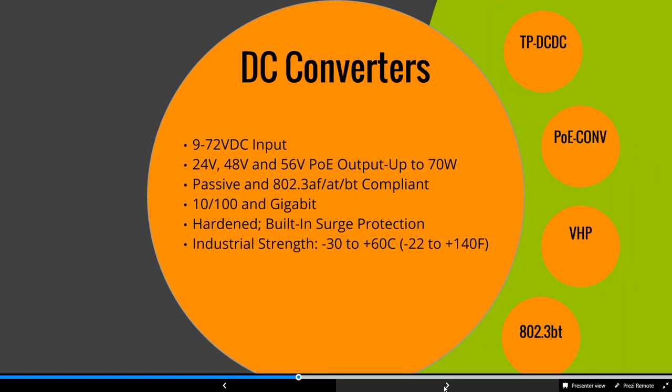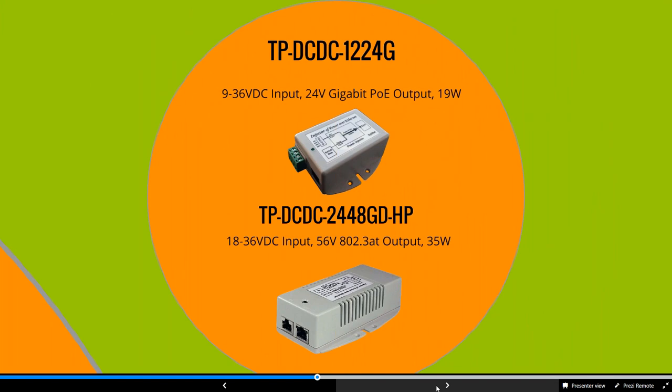We'll start with our DC-to-DC POE injectors — great for when you have a 12 or 24-volt battery bank but need POE output. These accept 9 to 72-volt input with 24, 48, or 56-volt POE output in passive and compliant options. One of our most popular parts is the TP-DCDC-1224G, which takes 9 to 36 volts in and gives you 24-volt gigabit POE out at 19 watts. This handles the majority of Cambium, Ubiquiti, MikroTik, and Mimosa devices that are 12-volt related.